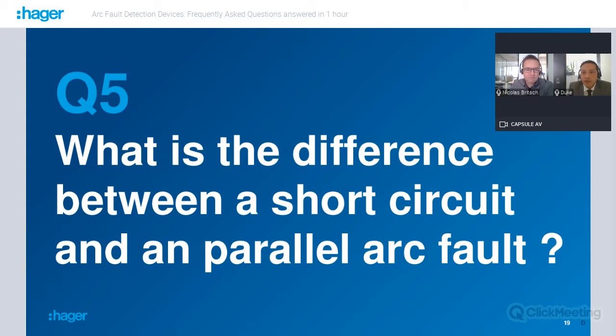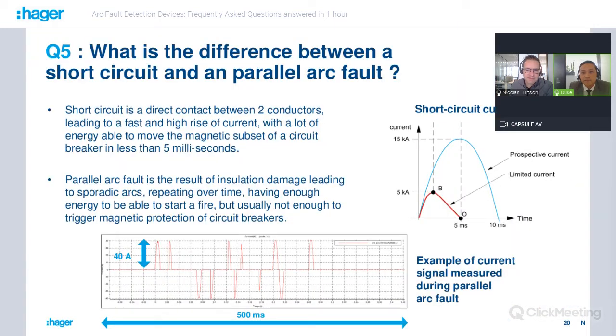So Nicolas, we already talked about AFDD definitions and arc faults. Now, what is the difference between a short circuit and a parallel arc fault? I think it's interesting for different people to understand this question. Yes, exactly, because sometimes people think that you are already protected with MCBs against parallel arc fault, but actually these are two very different kinds of situations. First, the short circuit is a direct contact between two conductors, leading to a fast and high rise of current with a lot of energy, able to move the magnetic trip of the circuit breaker in usually less than 5 milliseconds. So it's a very high value of current in a very short time. And you have the graphic here that illustrates this.